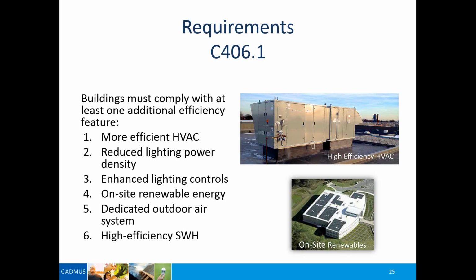LEDs are very, very easy to control also. So most systems now just have built-in controls. So you have a tremendously easy time just achieving lower lighting power densities. And the next item I mentioned, enhanced lighting controls. There's already quite a bit of control built into the lighting system in this code, as we'll see tomorrow. So that's probably not a very viable option, especially considering how low the lighting power density already is.